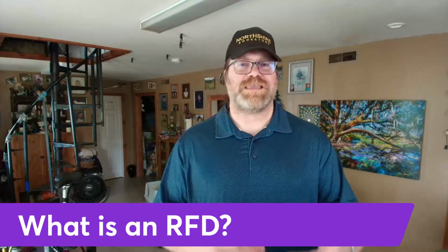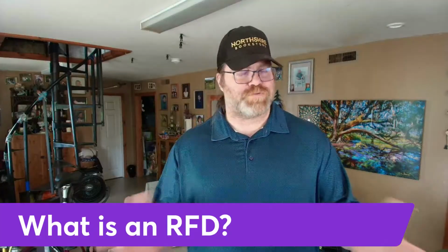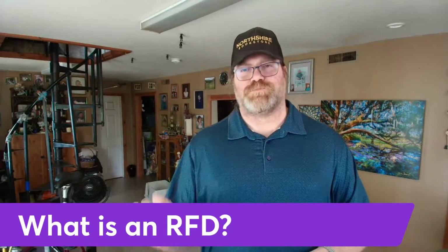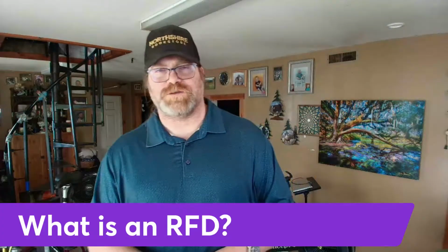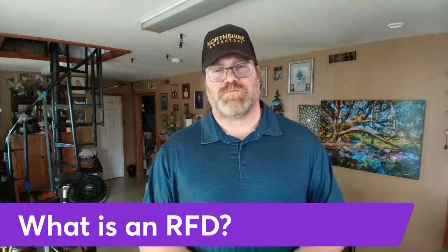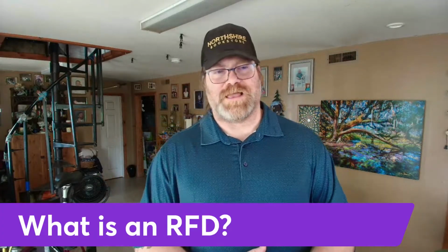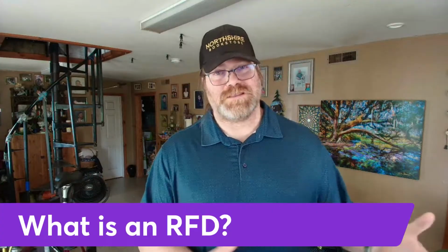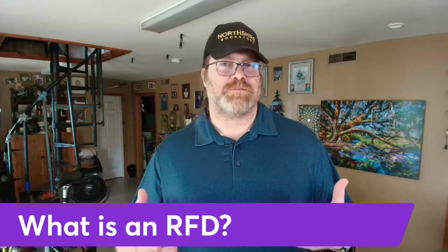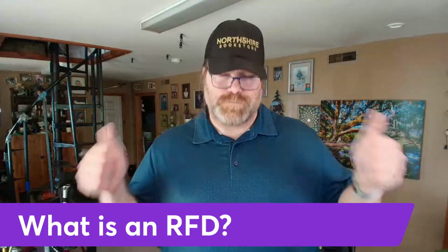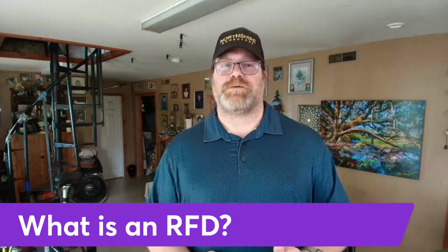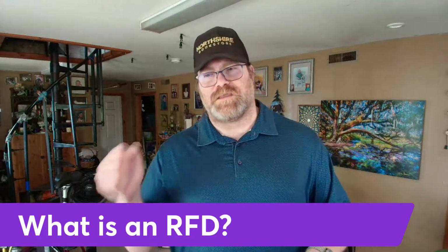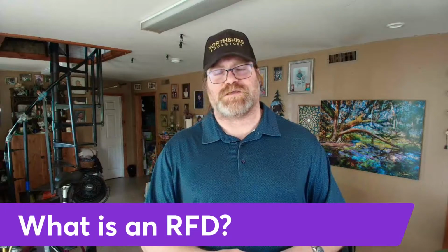So sometimes informal RFDs are perfectly acceptable. Yes, it's a combination product. Yes, it's CDRH. You don't need to do a submission. Save some paperwork. Save us some work. They'll gladly help you with that because it's informal. But sometimes you need the formal, especially when you're doing something novel that nobody's ever done before. So I hope I've answered everybody's questions about what is an RFD and how to do a request for designation.